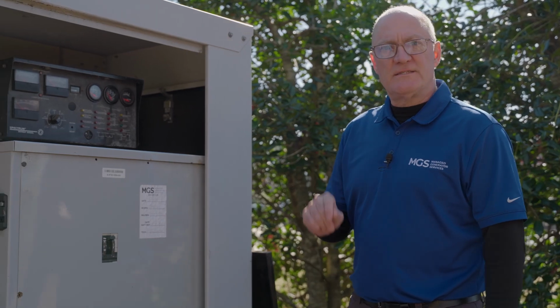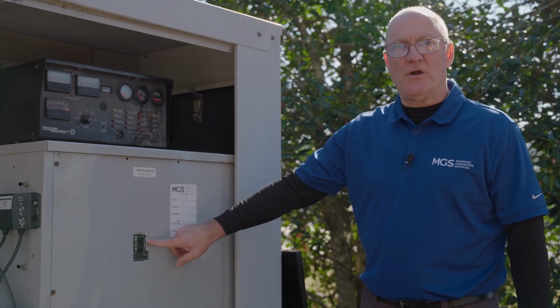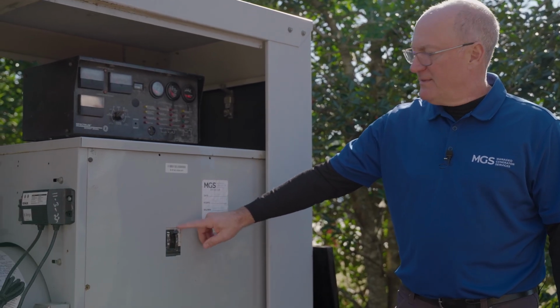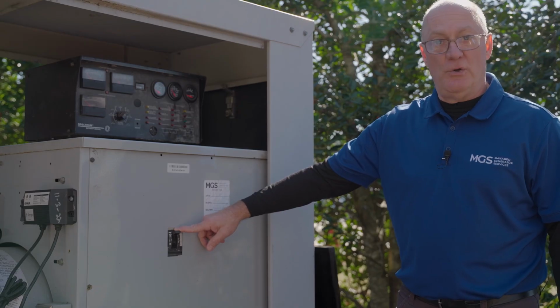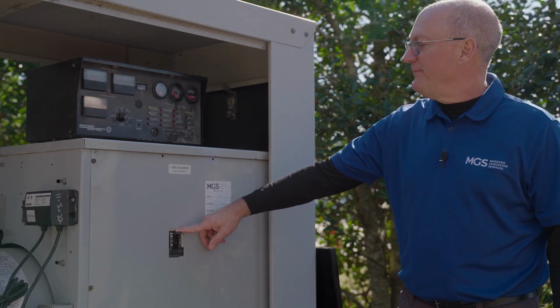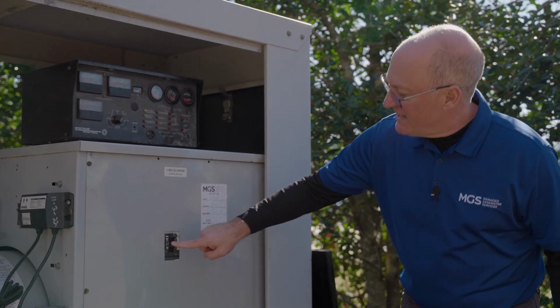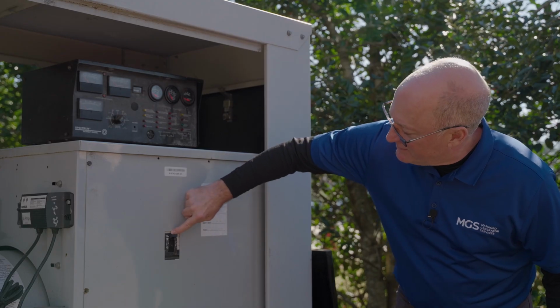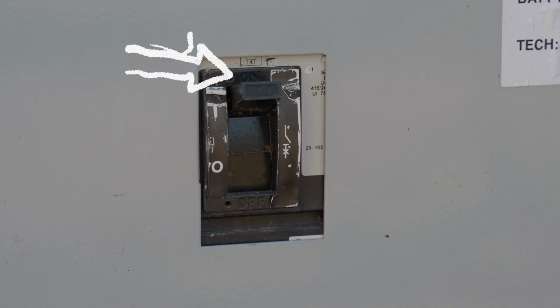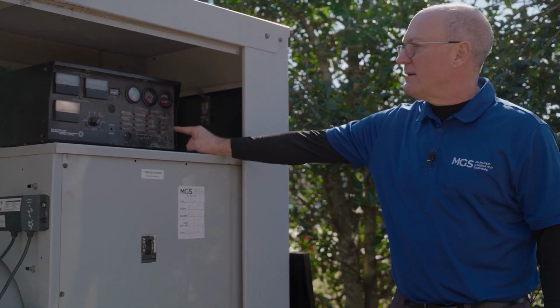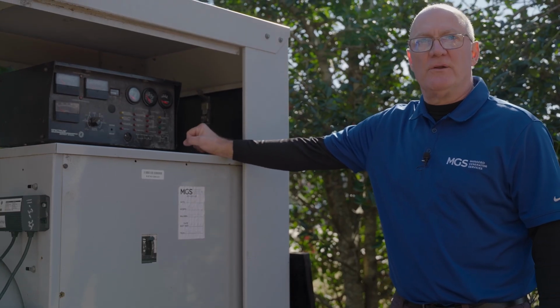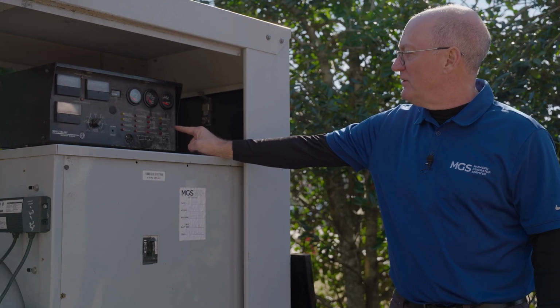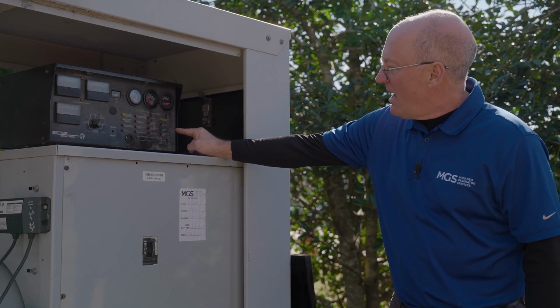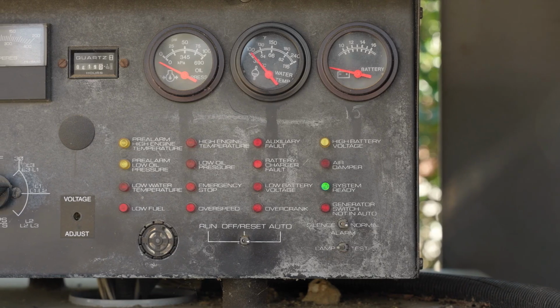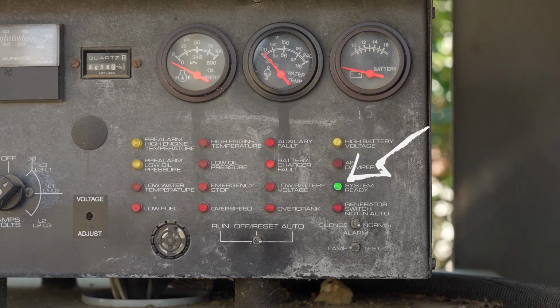The last two things that we're going to check, we want to make sure that our circuit breaker is in the on position or closed, whichever you like to call it. And then you can see here, it's got a writing here that tells you if it's on or off. We're in the on position. Then the last item is we want to check the generator control panel to make sure that we don't have any alarms. At this time, our green light for system ready says that it is ready to go.